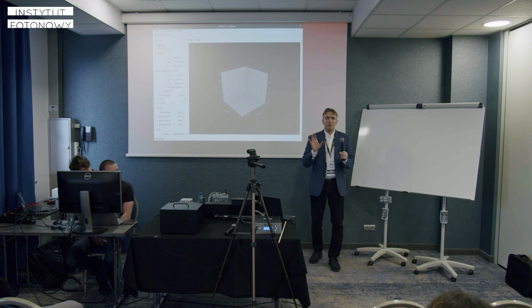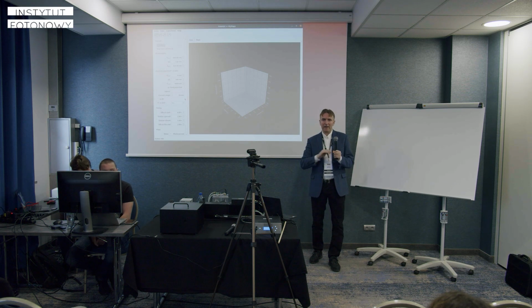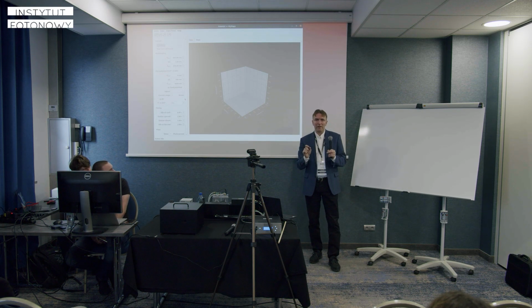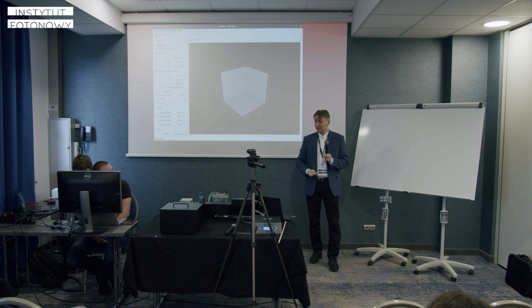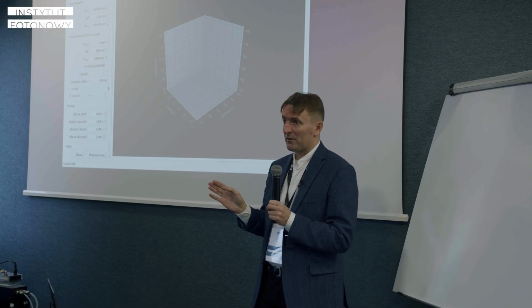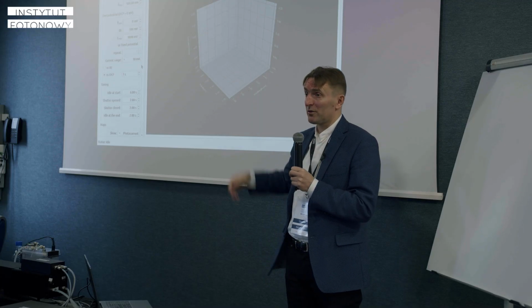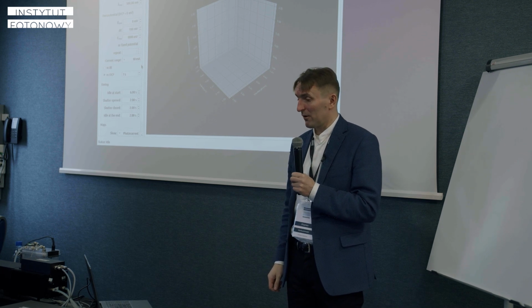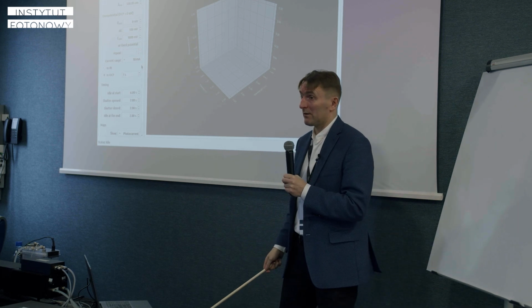So the measuring procedure is the following. You don't shorten the circuit. You try not to advance any current through it. Before you do anything, you attach just the voltmeter inside this potentiostat, which has infinite internal resistance, so no current will flow. It will measure the OCP, the open circuit potential. Then this software will plug it into the settings of your measurements, and with one click you can control already overpotential.